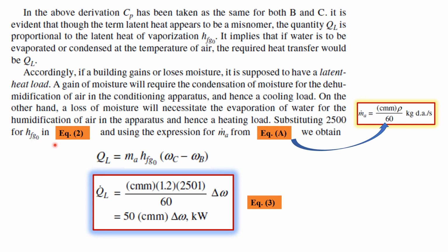So substituting 2500 for Hfg naught in equation number 2 and using the expression for mass flow rate of the dry air Ma, using this expression Ma equal to CMM into rho divided by 60, that is kg of dry air per second, where CMM is nothing but the volumetric flow rate in cubic meter per minute. So we express this latent heat transfer as QL equal to Ma into Hfg naught multiplied by omega C minus omega B. So Ma can be expressed in terms of this CMM and density. Density is known to us, it is 1.2. Ma is nothing but CMM by 60 into 1.2. Hfg naught is 2500 or 2501. Omega C minus omega B is nothing but the change in specific humidity, so it is denoted by delta omega. So finally we get an expression for the amount of heat transferred in the form of latent heating or cooling, QL equal to 50 CMM delta omega, and the unit is quite important, it is expressed in kilowatt.